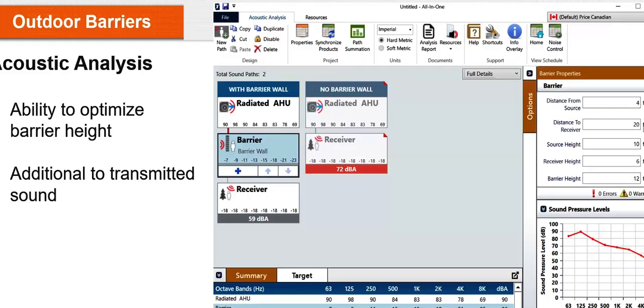The distance to the receiver, where is the line of sight? It could be a window 20 feet away. Your source height, so this specific radiated air handling unit or rooftop unit, it has 8 numbers. Remember those frequencies here. You have the loudest at 125 hertz. I'm going to need those 8 numbers. And in this case, you're saying that there is a window or someone standing outside at 6 foot tall at the ear level.